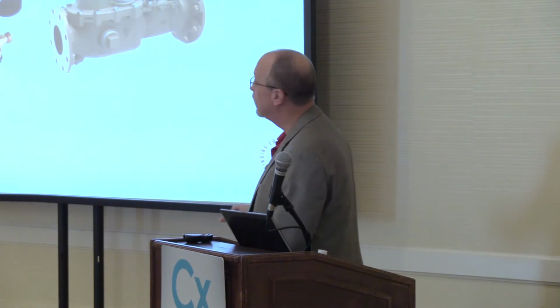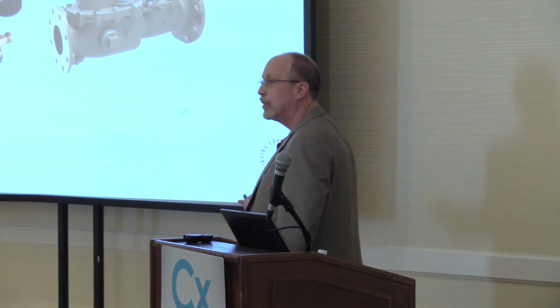But there's different kinds of water meters. There's a water meter on the outside of your house. Use this for smaller line sizes. This is a big boy here. This is what's in the front of this building there. This is called a compound water meter. A compound water meter is 2 water meters. We're going to look at this next, why that makes a big difference there, especially with an ultrasonic flow meter in your survey work.